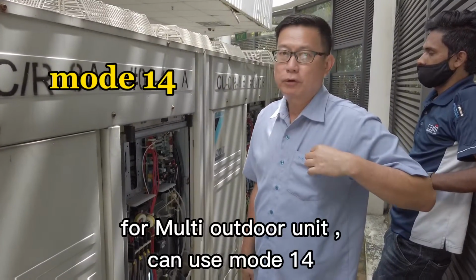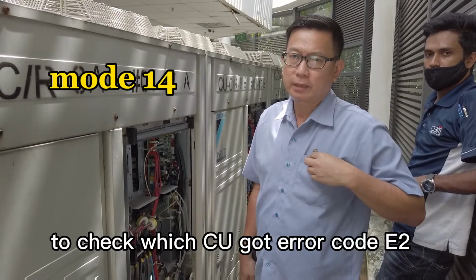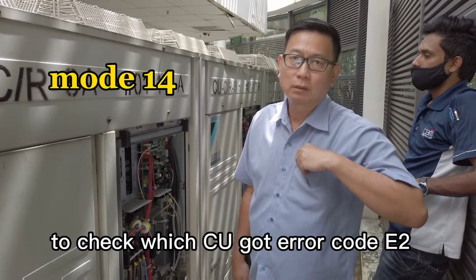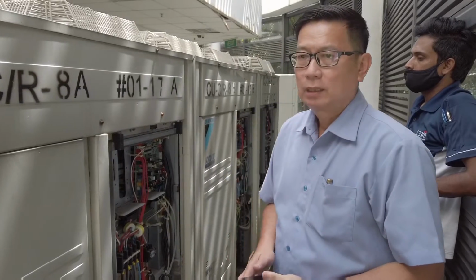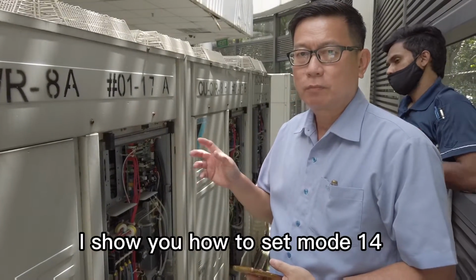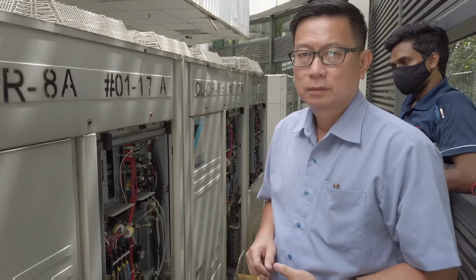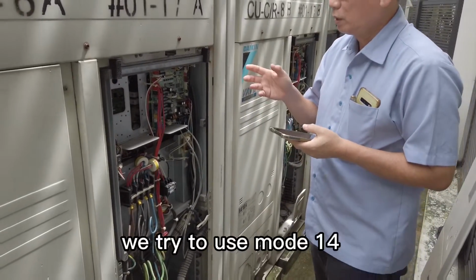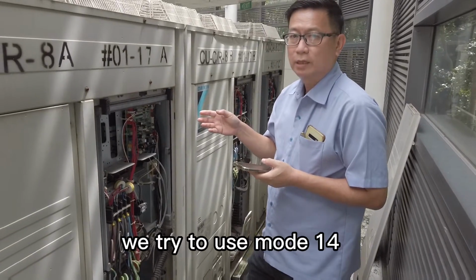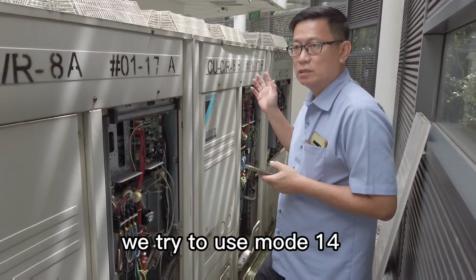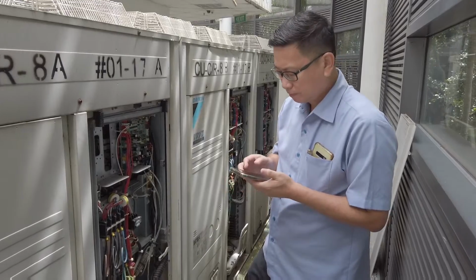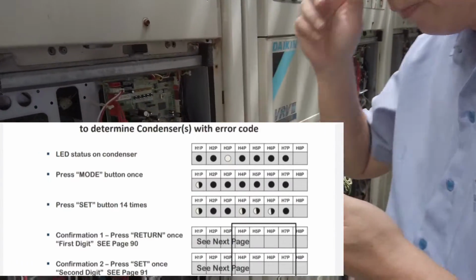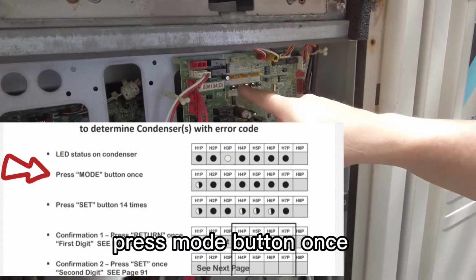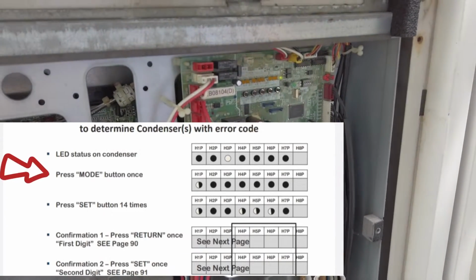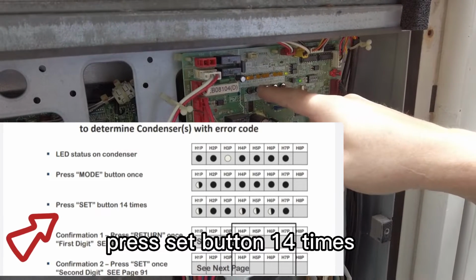For multi-auto unit, you can use mode 14 to check which CU has the error code. Later I'll show you how to press mode 14. Okay, we try to use mode 14 to check which CU is the problem. Press mode button once. Press set button 14 times.